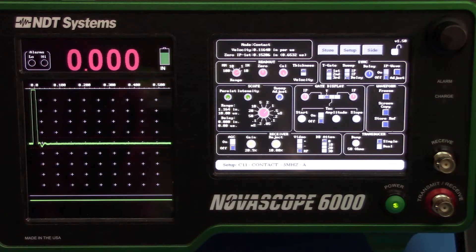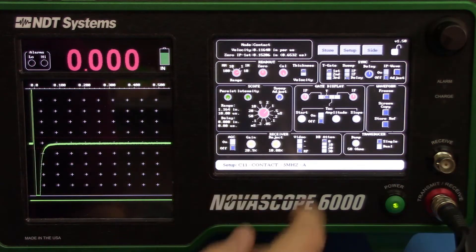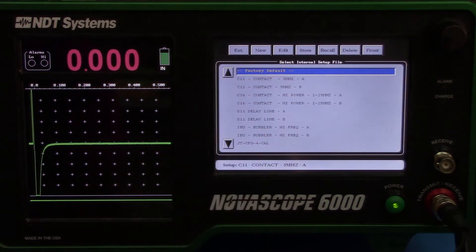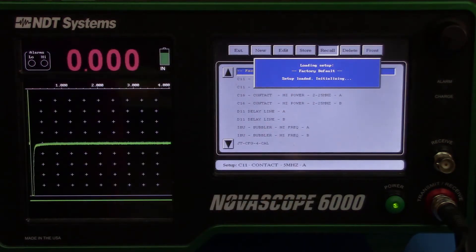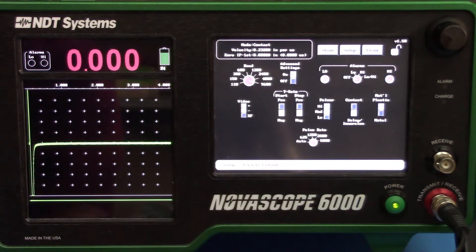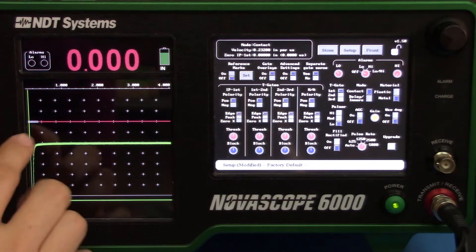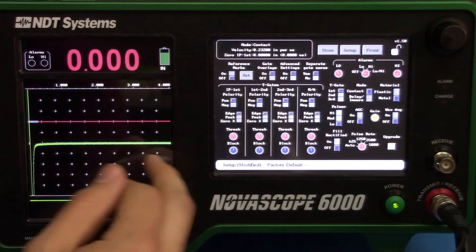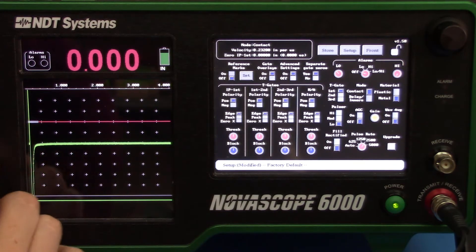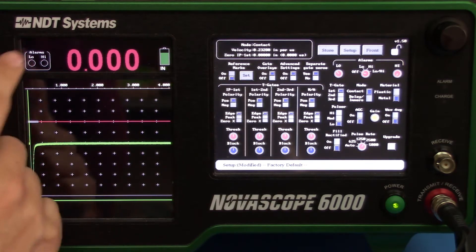Now we'll calibrate the NovaScope 6000 for use with our bubbler transducer and our wax shims. First, connect the probe to the unit. Then go to Setup and go to Factory Default at the top. Hit Recall — we're going to set this up from scratch. Go to the Side button and hit Advanced Features on. Turn on gate overlays. Now we have our trigger gate and the waveform. We're only going to be dealing with thicknesses from about 0.1 to 0.5 inches, so let's adjust the range down.